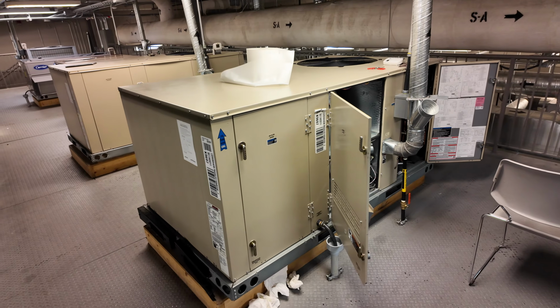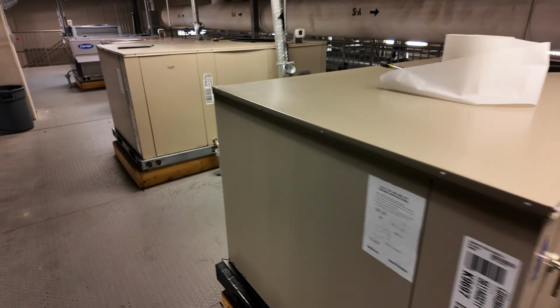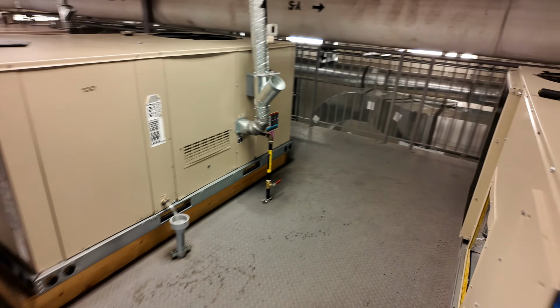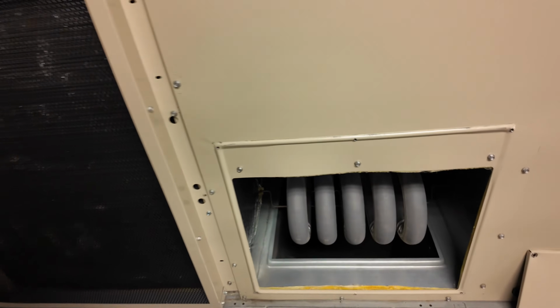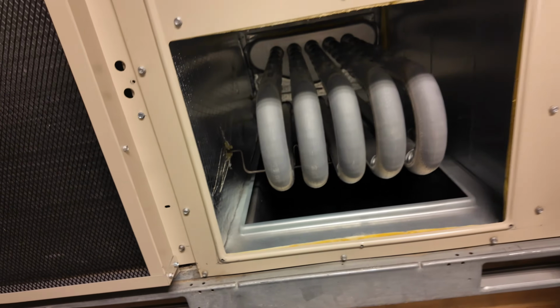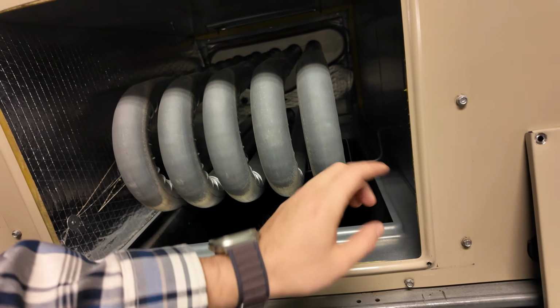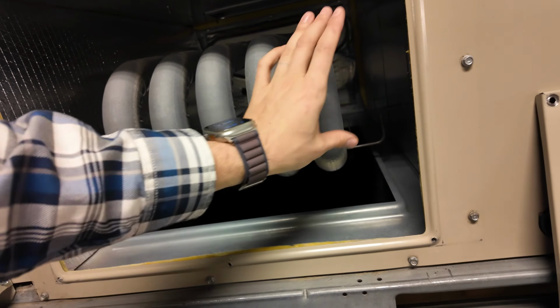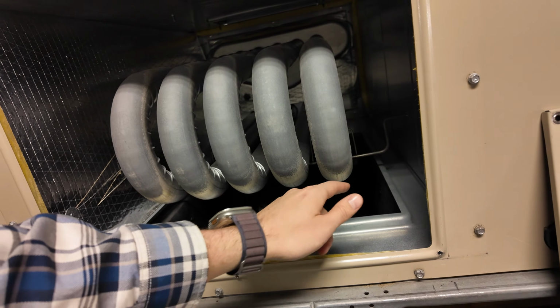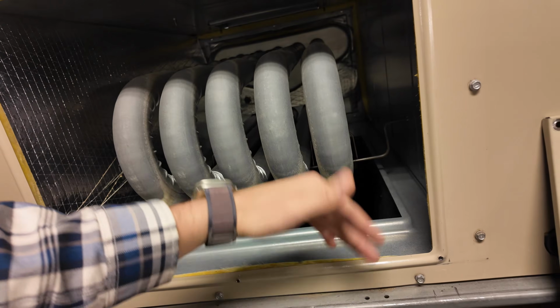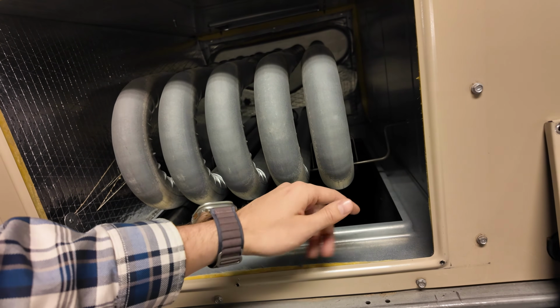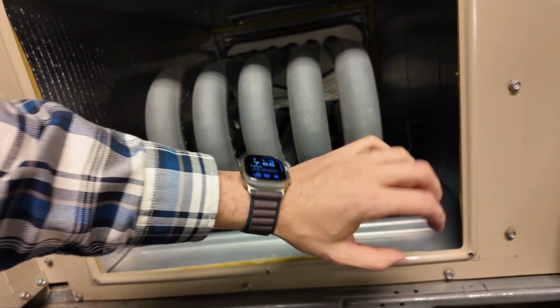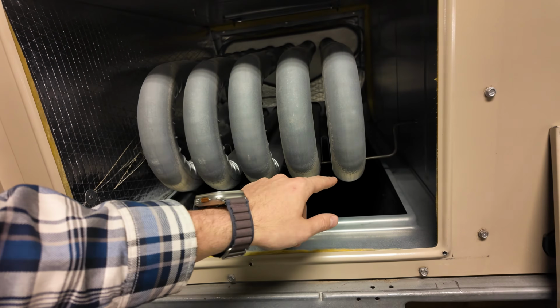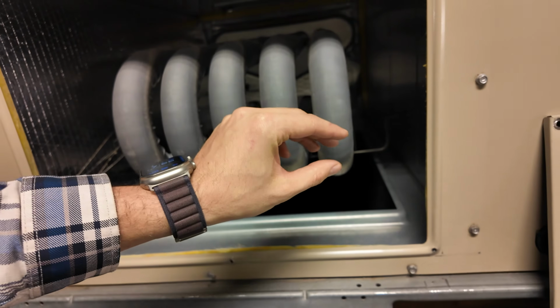Lennox, here we got a Lennox rooftop. They're only really notorious for cracking in one spot, and that is on the U-bend. So if you come around to the back, products of combustion shoot out the bottom and come over here, and all that heat basically hits this corner. And right here, when they bend the steel, and they actually bend this 180, it thins out this outer wall as it gets stretched the most. So this outer wall is the thinnest, and that's where the heat hits this wall.